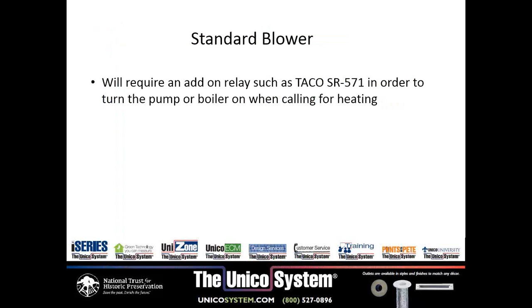If you use our PSC motor, by the way, our PSC motors are fine with hot water heating. It's just that you will need to get an add-on relay like a TACO SR-571.